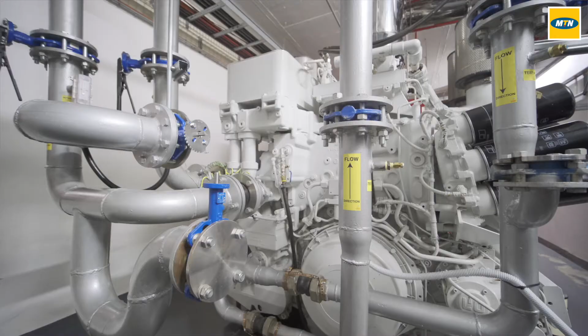According to the Uptime Institute, for Tier 3 on the white paper, only one of the paths needs to be active, and the other has to be passive. In our case, it's even better than that, we have both active at all times. We have a supply of diesel for up to 72 hours. Should the main power supply, Eskom, fail, your equipment will be able to run without any downtime.